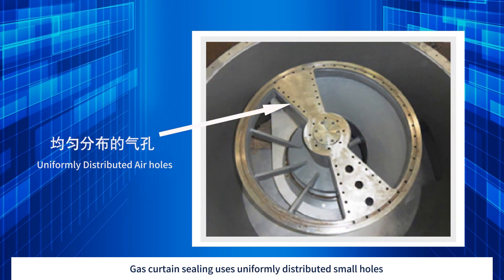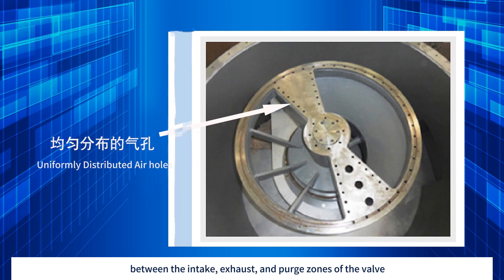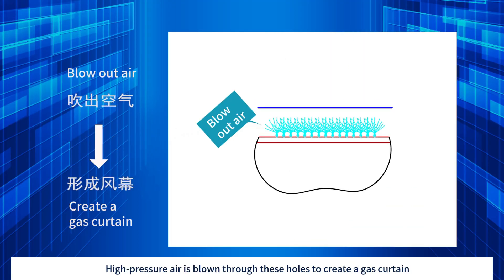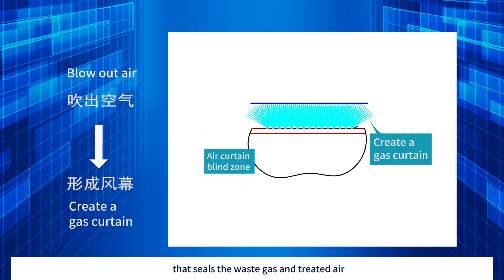Gas curtain sealing uses uniformly distributed small holes between the intake, exhaust, and purge zones of the valve. High pressure air is blown through these holes to create a gas curtain that seals the waste gas and treated air.